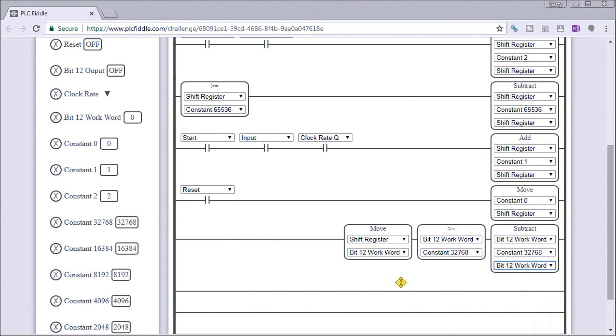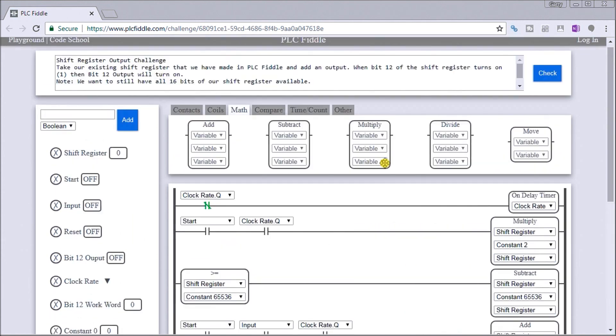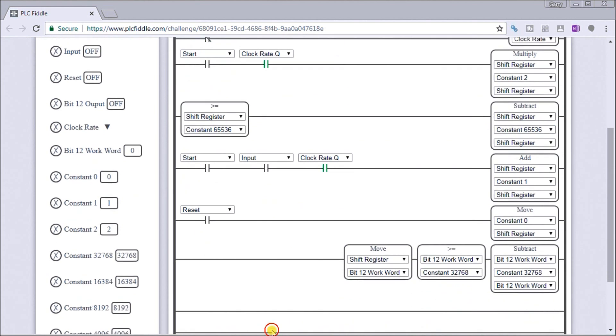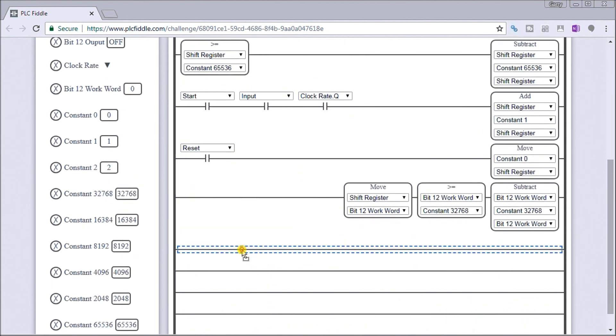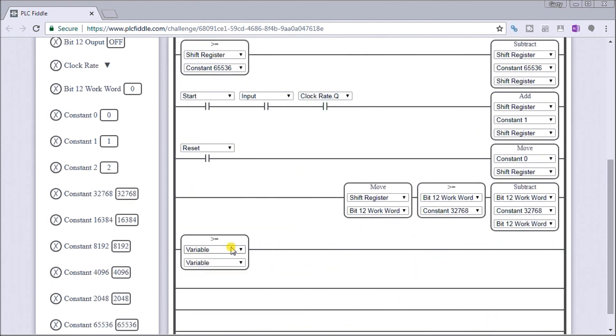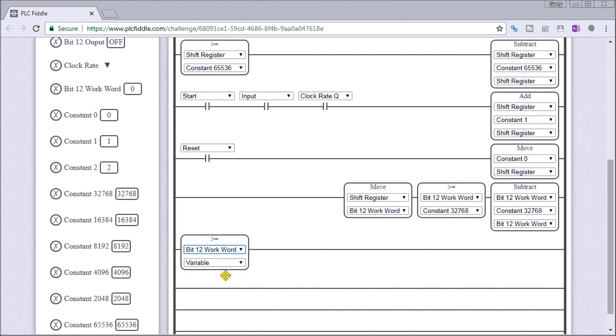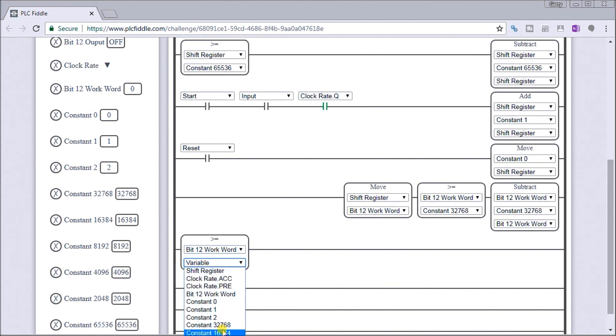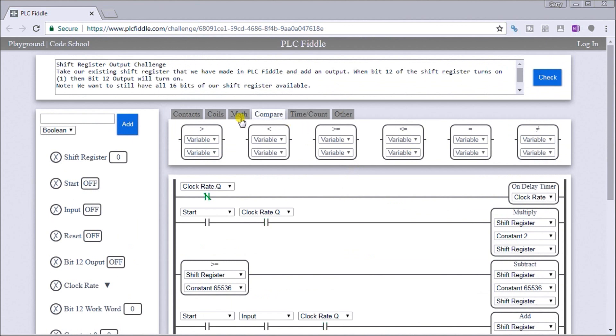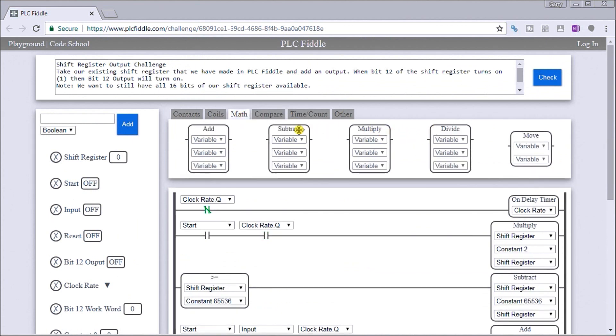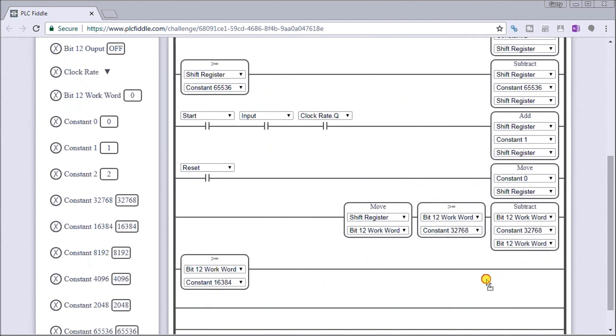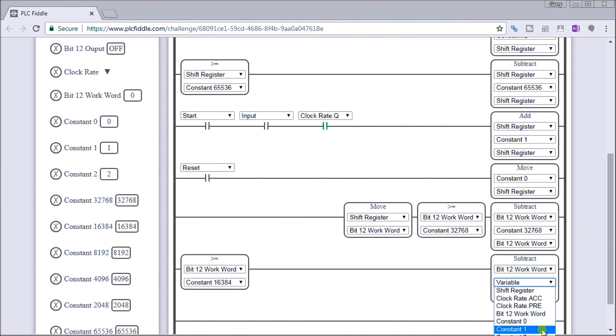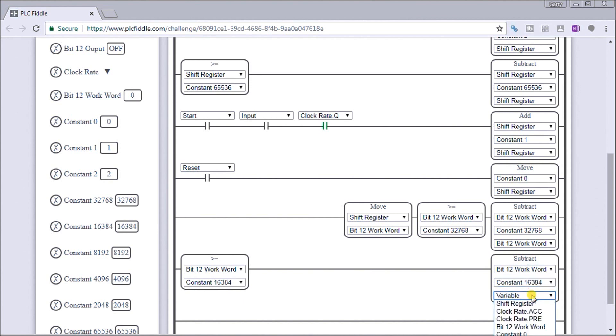So that takes care of one word. Now what we want to do is take care of the other three bits that are in there. So let's look at the compare again, and what we'll do is take a look at the 15th bit, and that variable will now be instead of 32, we're now looking at 16,384. And then we're going to do another subtraction. We're going to take that work word 15, we're going to subtract, and the constant is 16,384, and we're going to store that back into bit 12 work word.